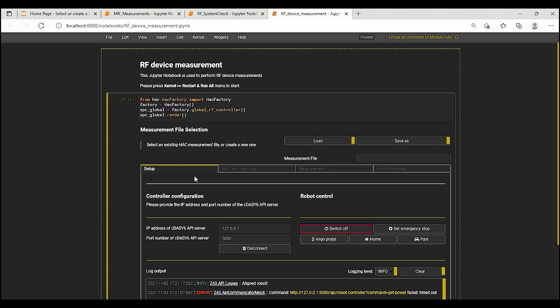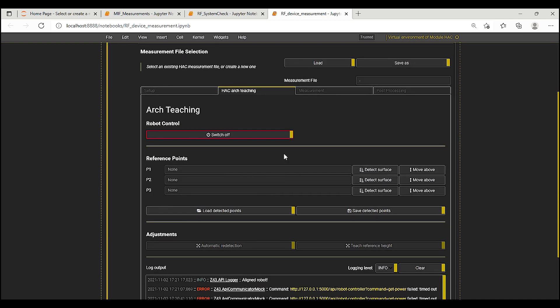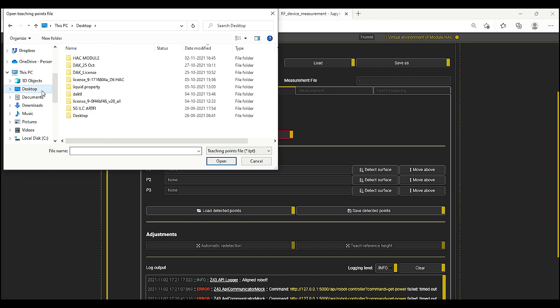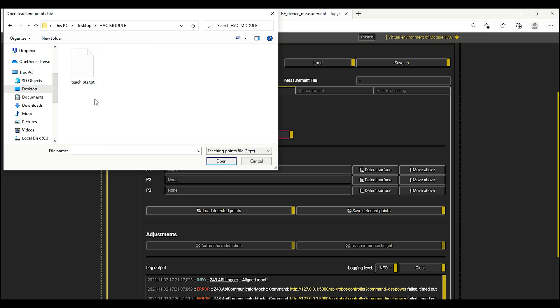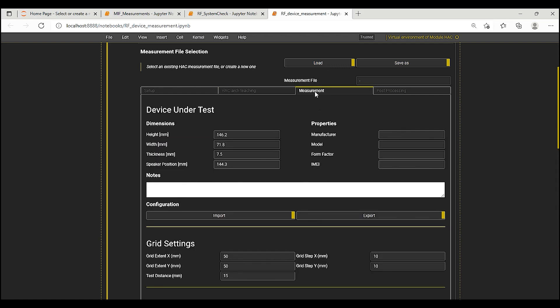This notebook has a tab display with setup tab for robot control, power on off and movement home or park and for teaching the light beam. I will now connect the software to the robot and move to the HAC arch teaching tab. The arch phantom is taught to the system by moving the probe manually with the help of the teach pendant to the three points P1, P2 and P3 that are marked on the phantom. For now, I will load these points from a file as these were taught previously during the RF system check testing. So now, I am ready to run the scan and move to the measurement tab.